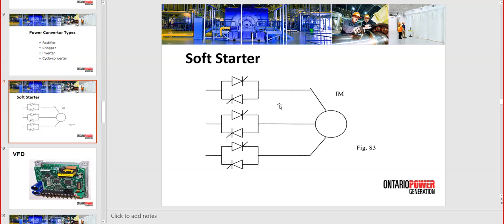Okay, so once again, the face of this soft starter may be the same as a VFD. It looks 3-phase in, 3-phase out, and has LED displays, LCD display and keypad and network and everything else, but it is not a VFD. And this is where people are confused, by using this soft starter as a VFD, or trying to solve problems that are for VFDs and not for soft starters.